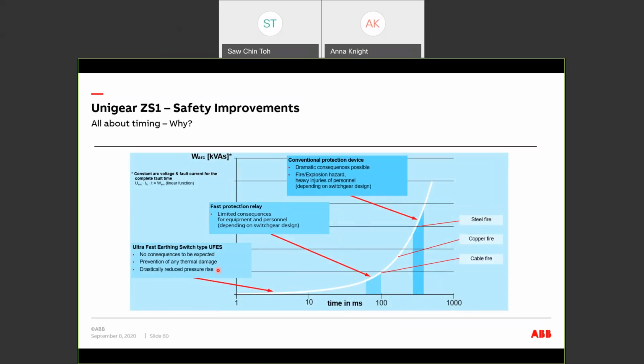As you can see, the energy grows exponentially after 100 milliseconds. Once we pass the 100 millisecond mark, the cable will catch fire, followed by the copper and the steel. The energy can reach up to 40 megawatts and the temperature around 20,000 degrees Celsius. The light and sound burst can also cause hearing and vision loss. This will definitely cause injury to the operator for non-internal arc tested panels. And this outcome is also not good even for internal arc tested panels, because the panel is damaged. A lot of cleaning needs to be done on site, and this would mean downtime for the customers.